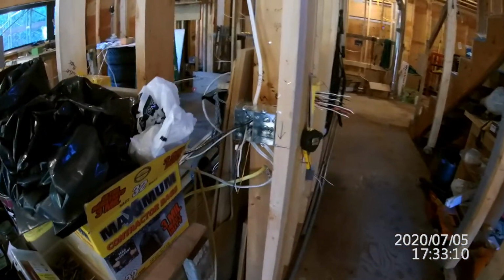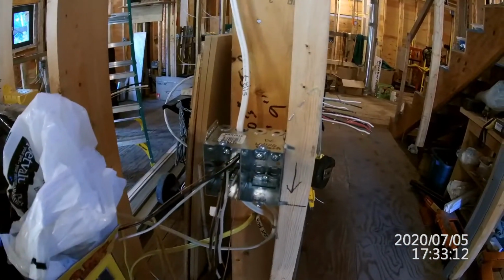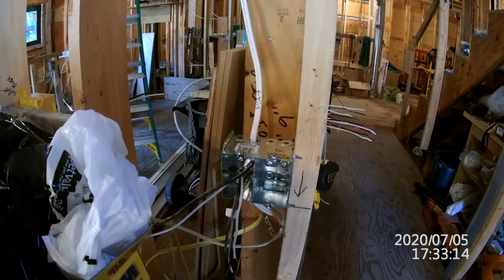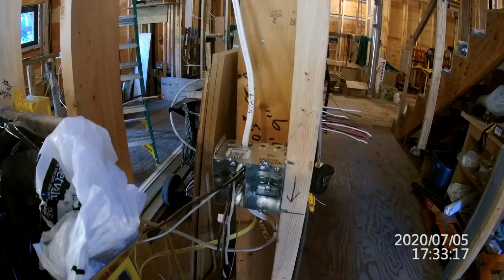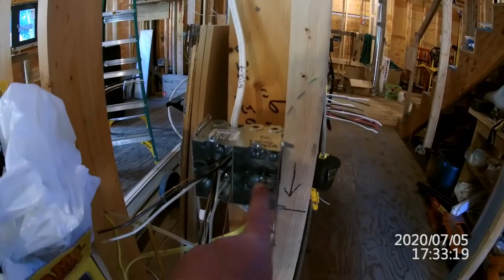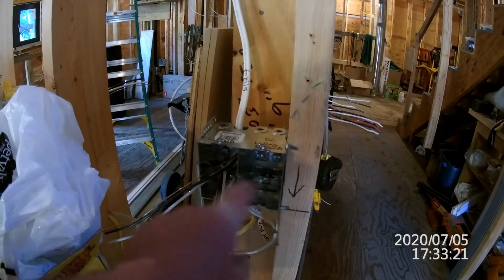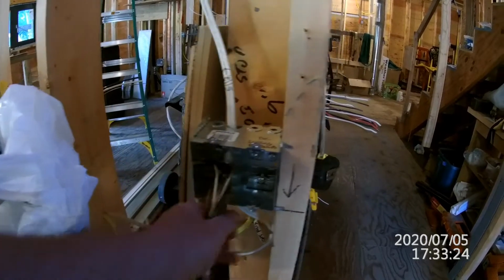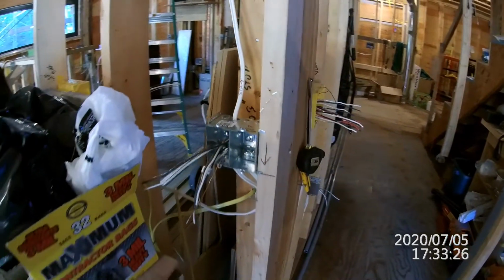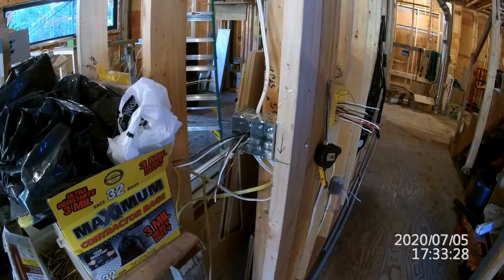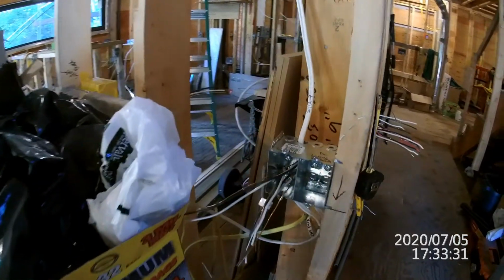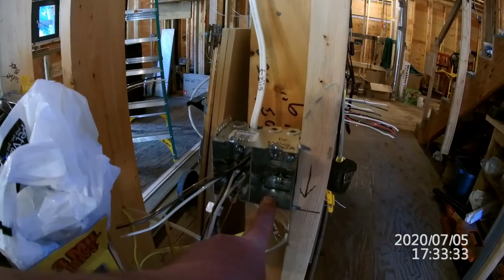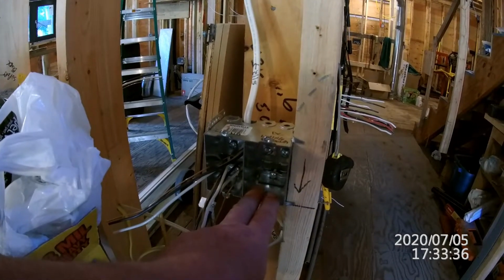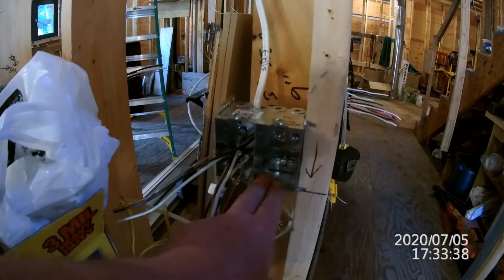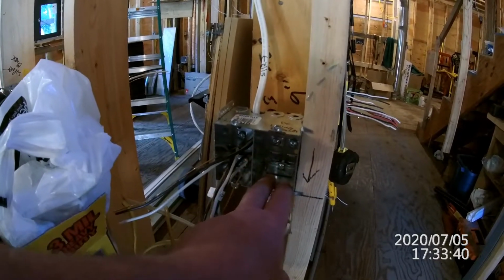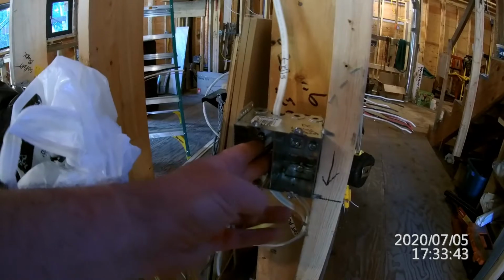So for instance, here's a box that used to be a 2-gang plastic. But in order to do class 1 wiring, you have to separate the low voltage DC from the higher voltage AC. That made things a lot more interesting because now, even though this is only going to have 4 conductors in it, I can't borrow the excess 2 conductors that are allowed to service this side of the bay.